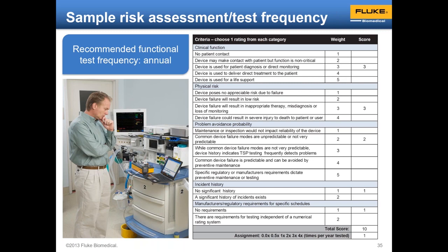If the answer to that question is not, I absolutely would test it, then think again and think with your heart and then use your mind, because it needs to be tested after every repair, and it needs to be tested when it first comes into the hospital, and it needs to be tested once per year to make sure that it continues to be safe and effective for clinical use. So once per year is how often.